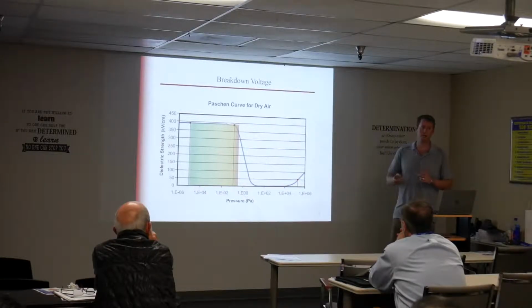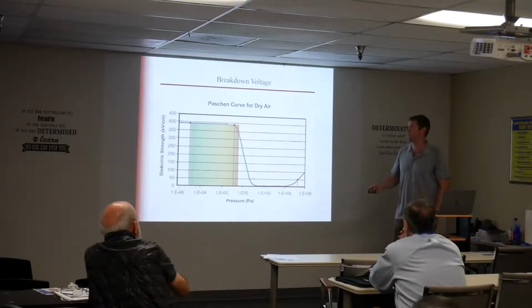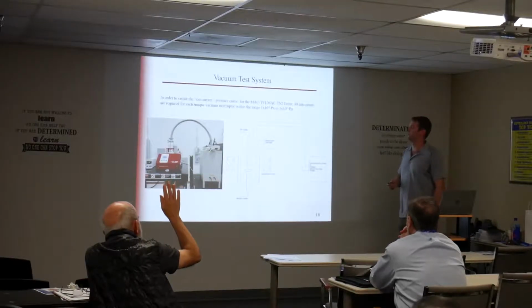Now you have 2 points with time in between. If those numbers haven't changed, it's not leaking. If it's changed a little bit, now you can determine the exact leak rate for that interrupter.